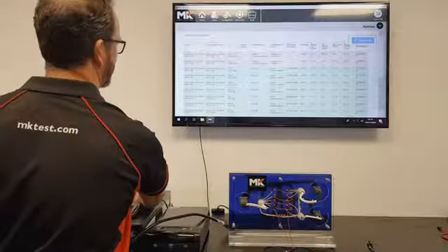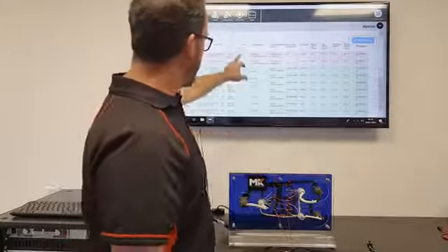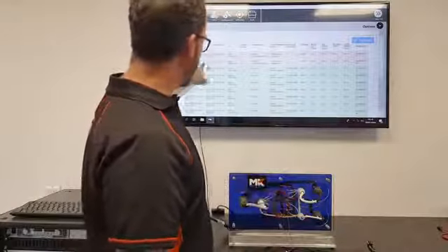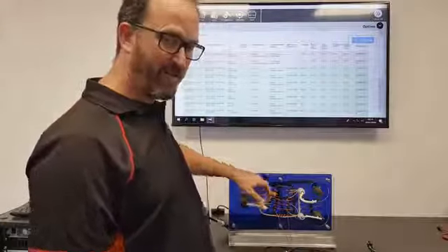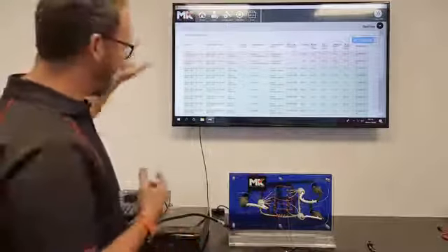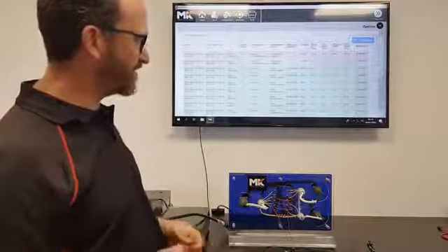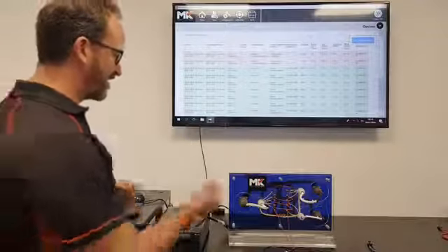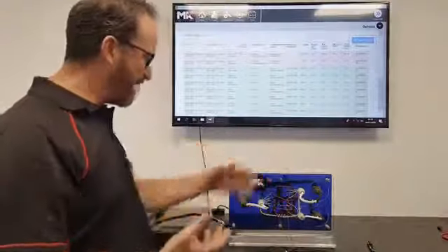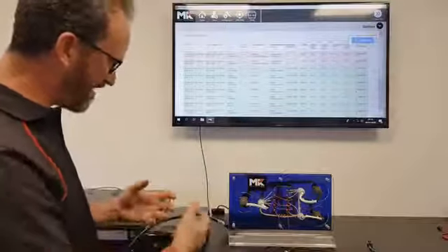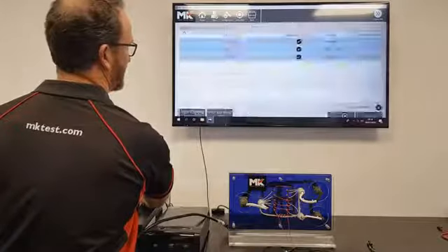And if we go to the insulation test, it's telling me that net A1 to B1, which is this first net, has failed to wall, and net A2 to B2 has failed to wall. So we know that between A1, B1, and A2, B2, these two nets, we have a breakdown. Most common failures tend to be to ground, and in that case, it would tell you that A1 to B1 to ground has failed. So again, very, very good, clear diagnostics as to the nature and location of that failure. So let's repair my harness. I've gone in there and I've cleaned the debris out from the inside of the connector, or I've had a look and I've repaired the insulator where it's cracked. Let's go home, run this whole test again.